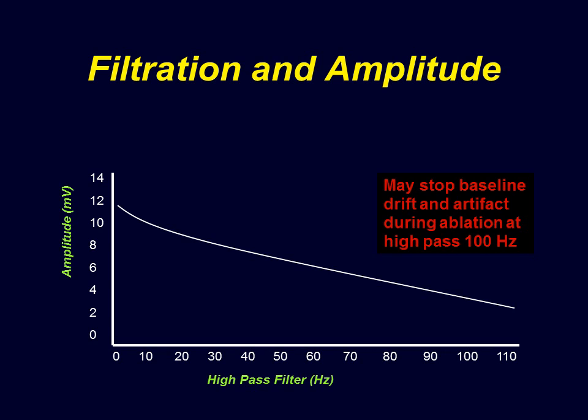With high-pass filtering, you can stop the drift and only see the waves of interest. The majority of modern labs have 128 channels, so you can plug in many things. Amplifiers gain amplitude up to 10,000, although noise may interfere. The high-pass filter stops baseline drift and you may have to adjust between 30 to 100 depending upon the grounding in the lab. There is also an isolation amplifier to isolate the electrogram from the patient, and a low-pass filter to remove environmental noise.